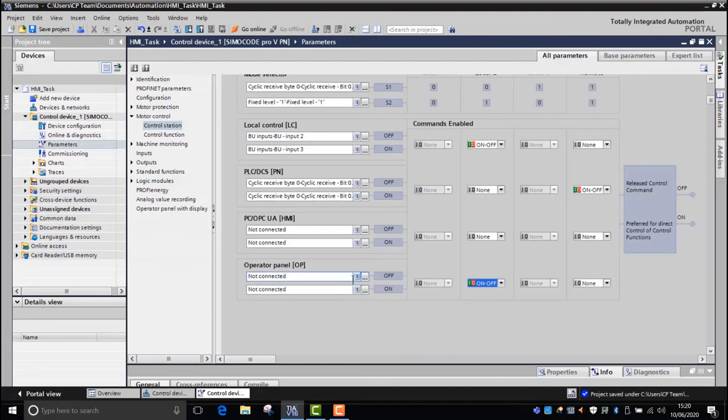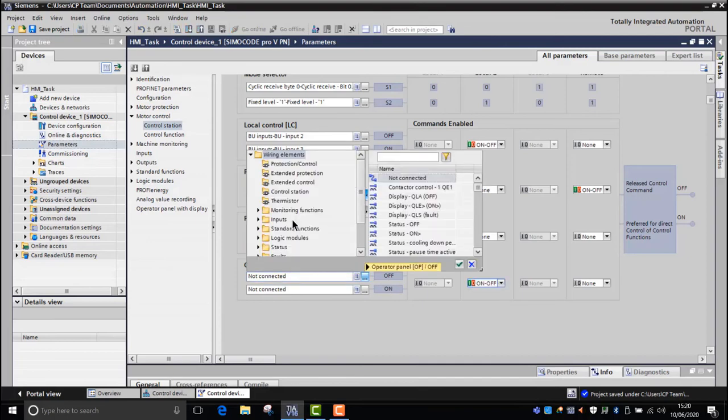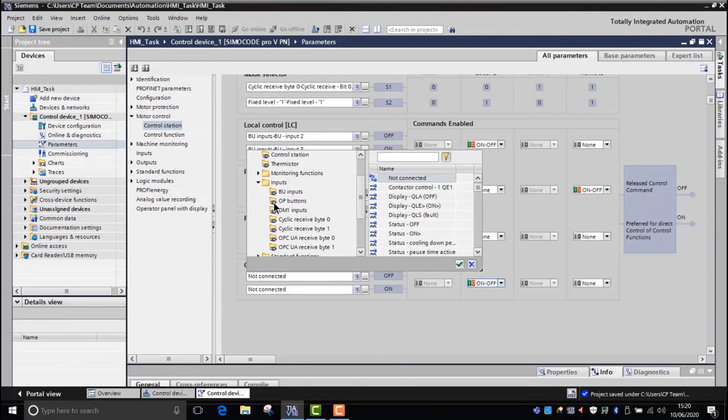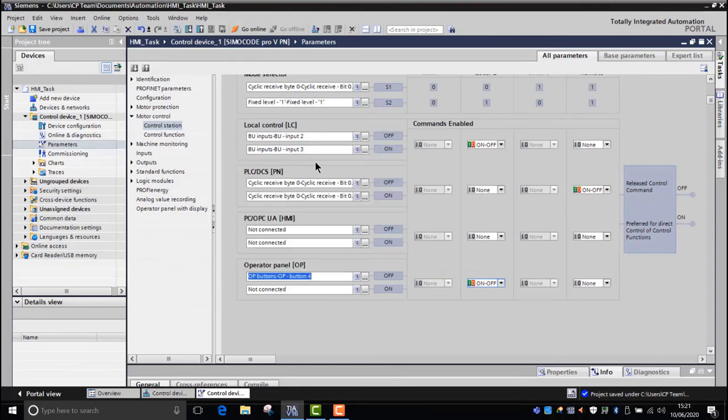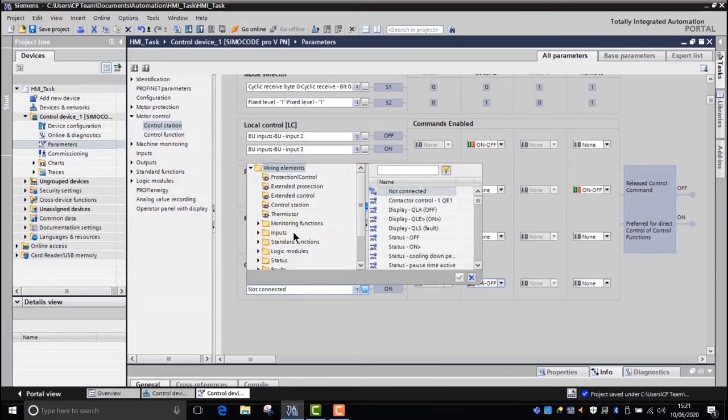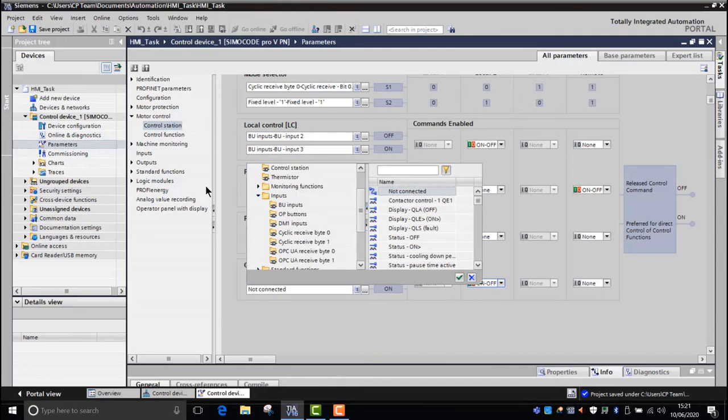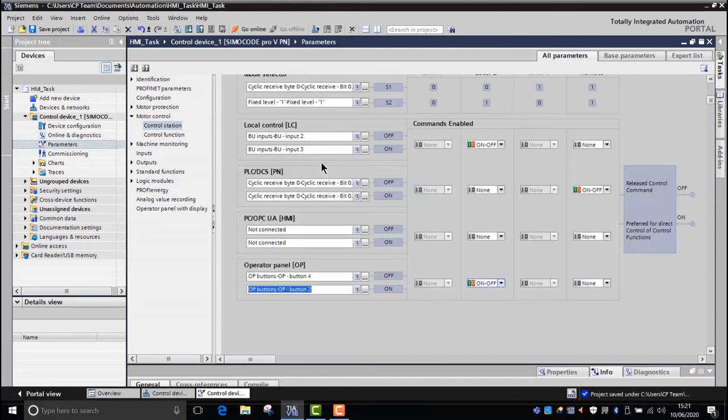So the operator push button we want for off will be OP4. So if you go into inputs, OP push buttons, OP push button 4, that will now be initiated of the off command. And the on command we want OP2. Inputs, OP, OP2. So once that's done, we can then start having a look at how we illuminate those push buttons.